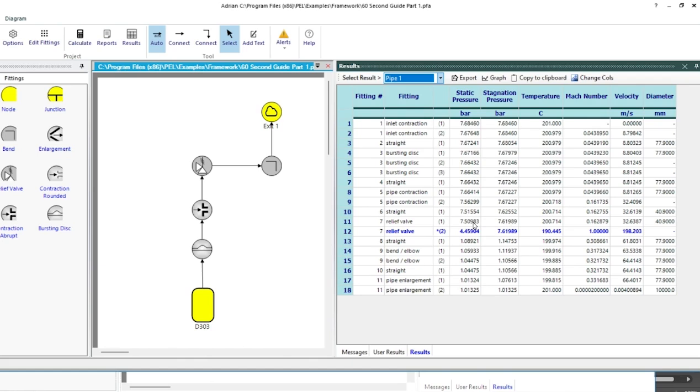So if you read the pressure with a pressure gauge on the side of the pipe, it would be a slightly lower pressure. But obviously we don't want to include that extra 0.1 into our inlet pressure loss, because that's not an irrecoverable loss due to friction. That's just Bernoulli being Bernoulli. So we need to make sure we pick the right pressures up, and that's what ADRIAN does.